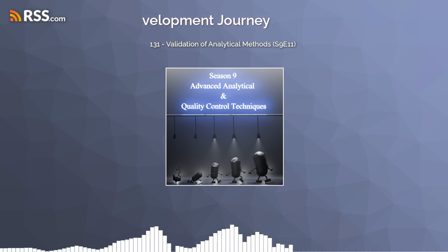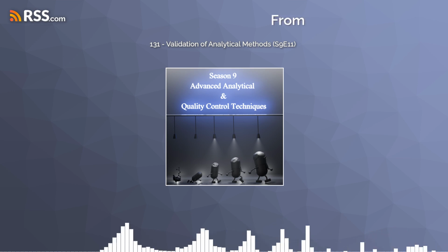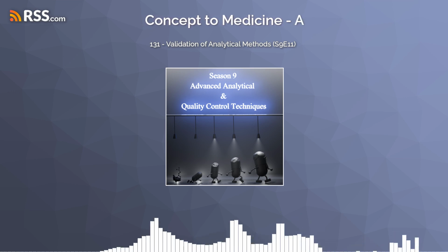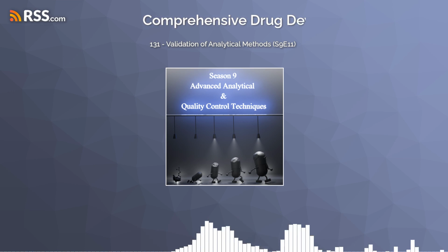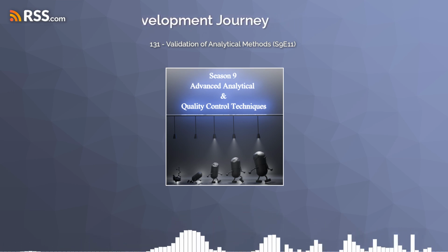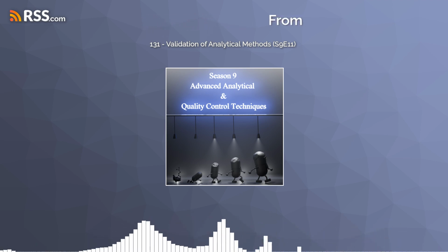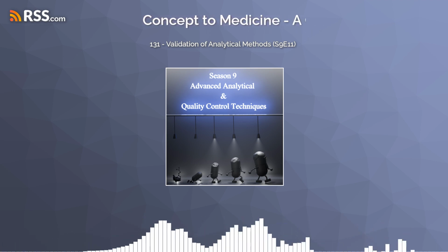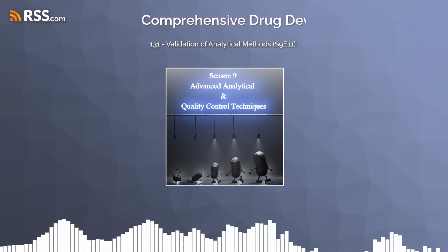And interestingly, the ICH Q2R1 guideline, which is kind of the Bible for analytical method validation, Yeah, ICH, that comes up all the time in these materials. It does, and for good reason. Anyway, it mentions that if you've really nailed down reproducibility, you might not even need to worry about intermediate precision. Oh, interesting. But in practice, particularly when you're transferring a method, the receiving lab will usually do their own intermediate precision studies. Okay. And both labs will generate reproducibility data just to be absolutely sure everything is consistent across locations. That makes a lot of sense.